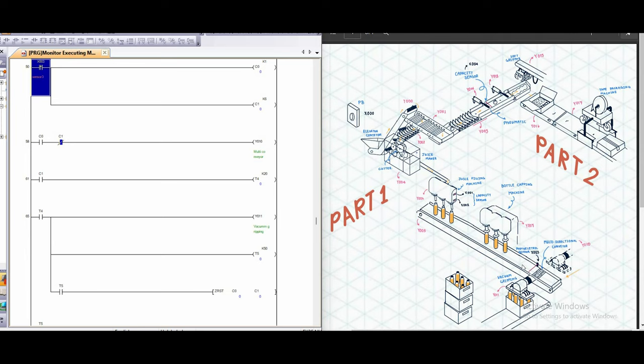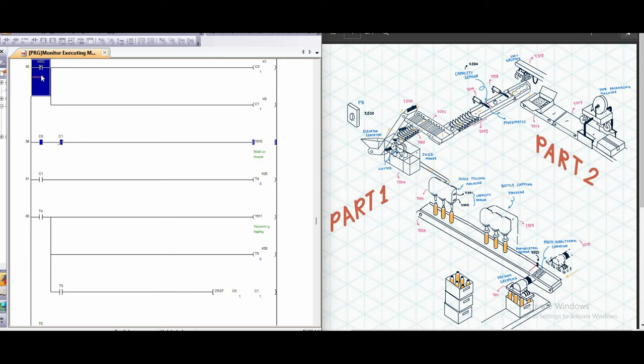For packaging station, the sensor x3 will be installed to detect the juice bottle. So when the sensor x3 is detected for the first time, the multi-direction conveyor y10 will start to work. And once the sensor x3 detects 6 bottles, the multi-conveyor will stop working for 2 seconds and then the vacuum gripping y11 will start to work by gripping the bottle to put in the box and it will work for 5 seconds.